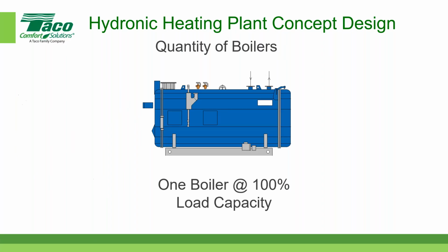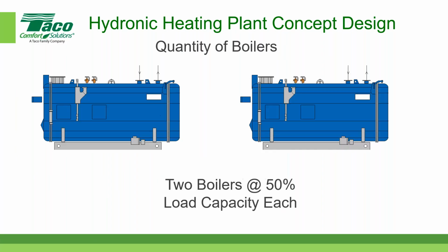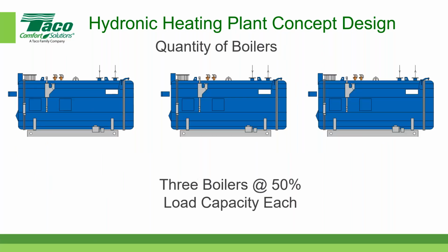So how many boilers do we want? Well, one possibility is to put in one boiler at 100% load capacity. Another possibility is to put in 2 boilers, and you could make those boilers 50% each, or you could consider making them 67% each. So a 2 boiler arrangement is a very popular arrangement today. 3 boilers.